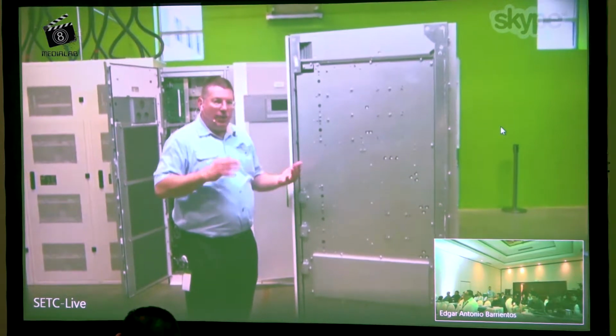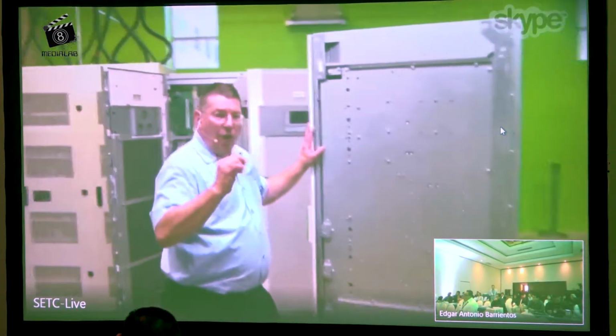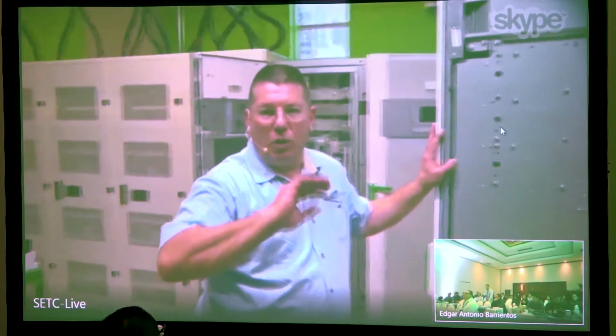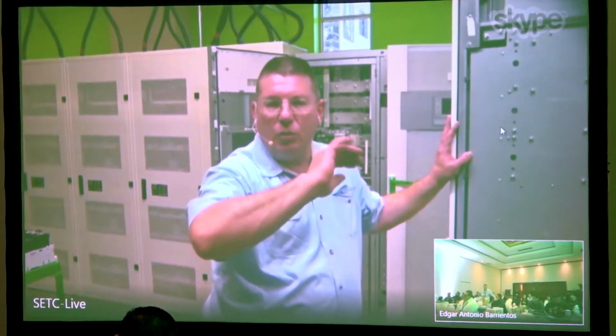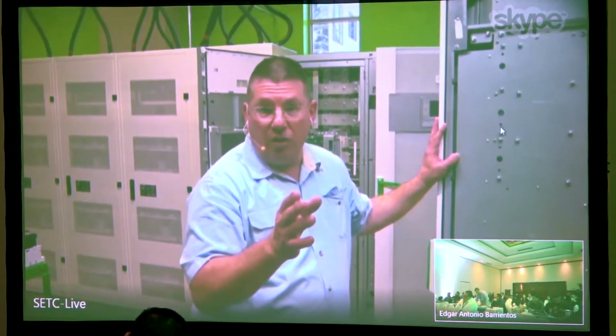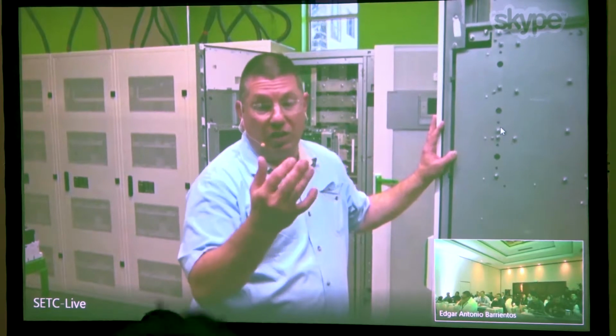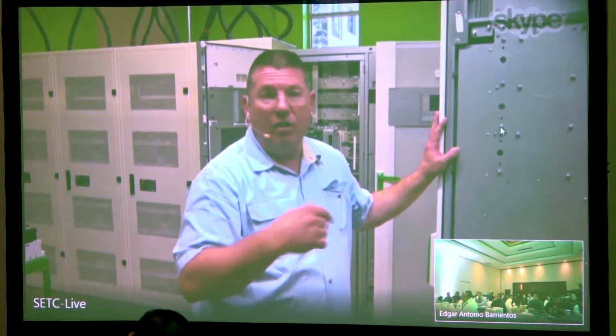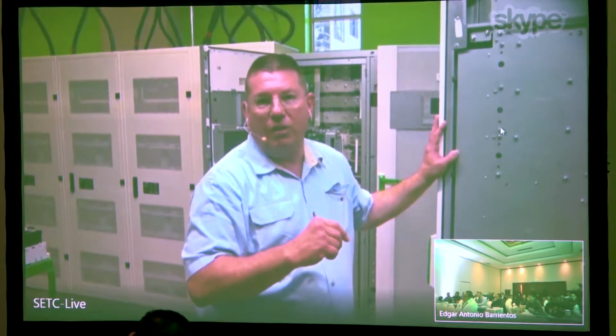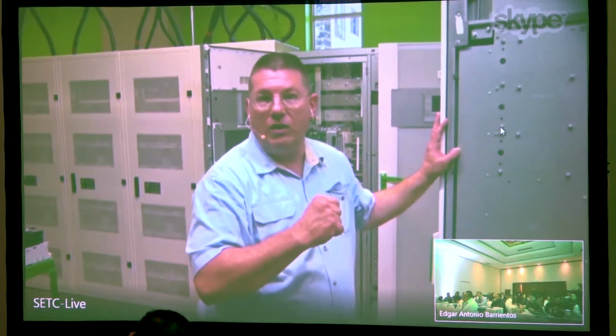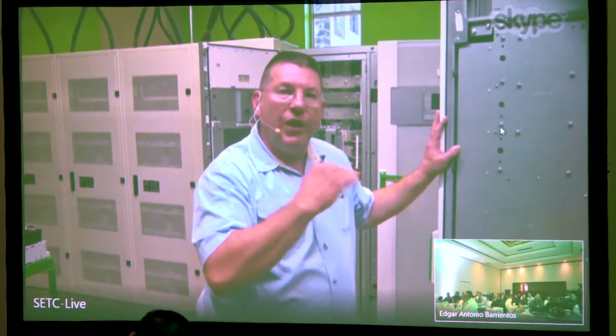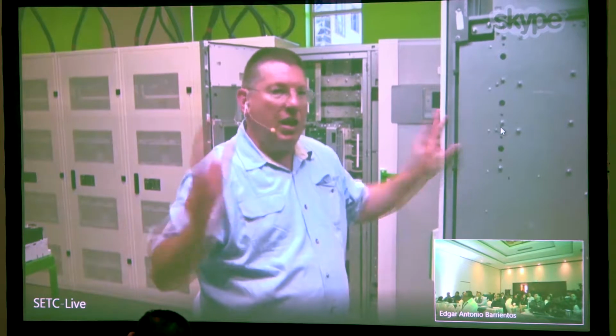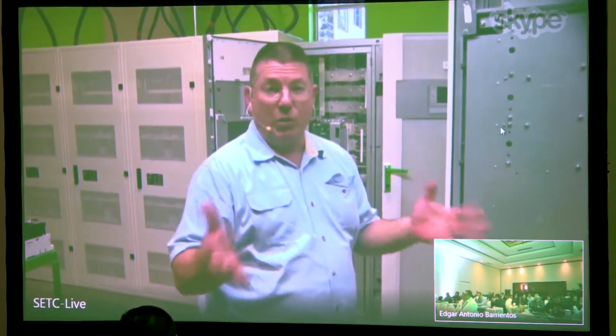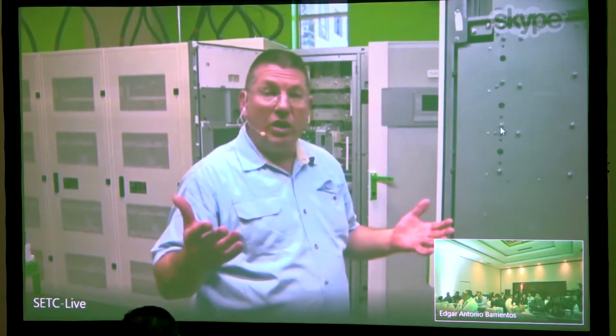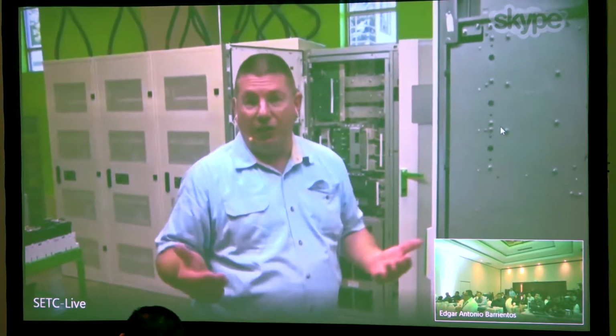Now, the UPS is also very, very efficient. So at low loads, roughly 30% load is where we start to achieve our 96% efficiency. We go up to about 96.4 in double conversion. In E-conversion, which is another operating mode, it's unique to Schneider, we actually achieve a 98.4% efficiency on this unit. So even at low loads, very efficient. So if the customer said, hey, we're going to do it all at once, we can have a highly efficient UPS then, or hey, we're going to expand later, we just don't know when that is, we're good there too, because it's easy to expand and highly efficient as well.